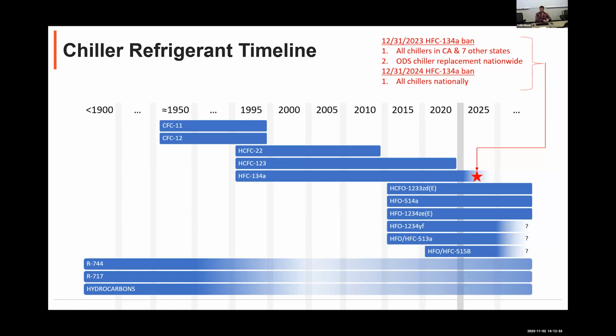And I should mention, the 513A works very similar to 134A. So the good thing about it is all the equipment developed around 134A can utilize 513A today. It's not going to be phased out in the next 1 to 2 years. 10 years from now, we're not sure. That's the good thing about that refrigerant. But the bad thing is the 2 substances that its major components are. And also its GWP is still relatively high. It's around 600, where the current limitation is 700. These other HFOs are all in the single digits.